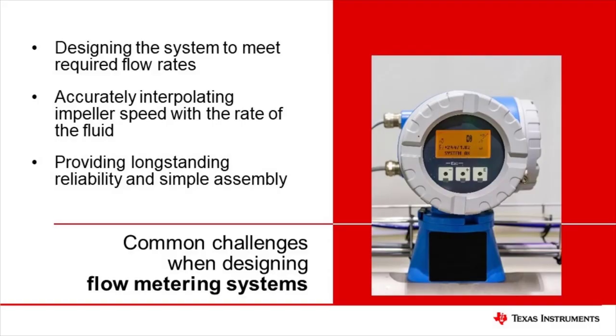It is important to consider mechanical design elements when creating a flow meter, as these characteristics can translate to mechanical errors that dictate the performance and accuracy of the meter. One of the main components to consider is the desired sensing range, as this will influence the impeller size implemented into the system. The impeller size regulates the minimum and maximum flow rate that can be handled by the flow meter.